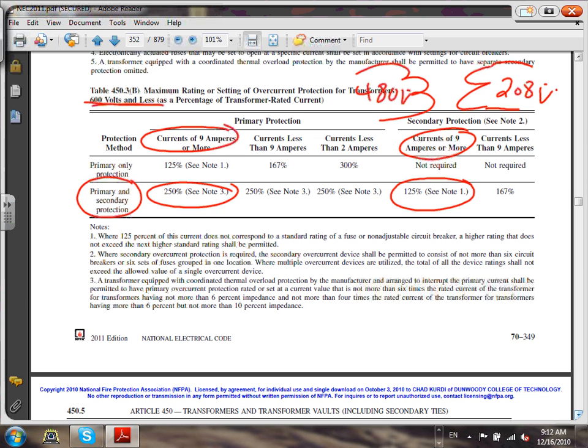Let's just do primary and secondary now. But that's a very good application where you can have primary only protection. So your primary protection will be right here for the transformer primary and for the secondary conductors, but your secondary conductors will be landing on a main for the panel. Main for the panel. Okay, any questions, guys, about this table? Everybody knows how to use this table.